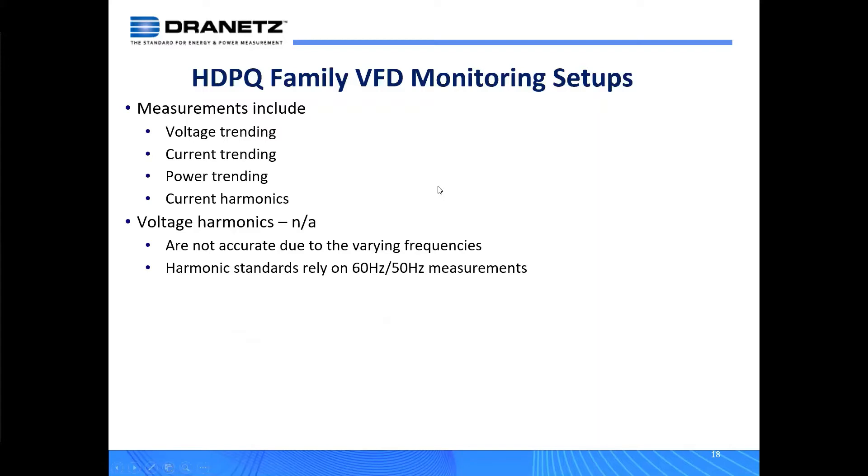The HDPQ family provides voltage trending, current trending, all the power parameters, and current harmonics. But it's important to share what is not provided: reliable voltage harmonic measurements. That's because IEEE 519 and IEC 61000-4-7 are dependent on a 60 or 50 hertz system to be measuring.